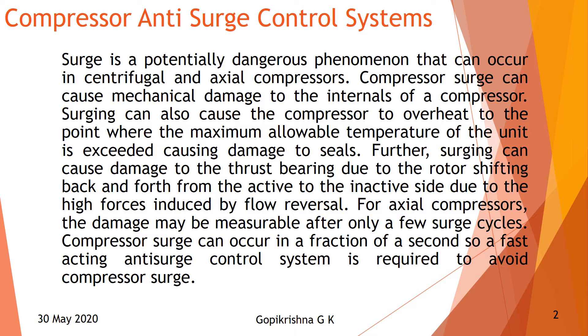Surge is a potentially dangerous phenomenon that can occur in centrifugal and axial compressors. Compressor surge can cause mechanical damage to the internals of a compressor. Surging can also cause the compressor to overheat to the point where the maximum allowable temperature of the unit is exceeded, causing damage to seals. Surging can also cause damage to the thrust bearings due to rotor shifting back and forth from the active to the inactive side due to the high forces induced by flow reversal. For axial compressors, the damage may be measurable after only a few surge cycles.